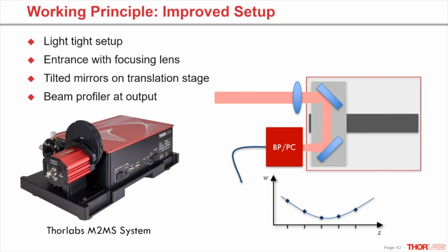And finally, after at least 5 points around the focus and another 5 points beyond the Rayleigh length, before and after, the beam waist can be determined and compared to the ideal Gaussian beam waist under the same divergence. And finally, the M-square can be calculated.